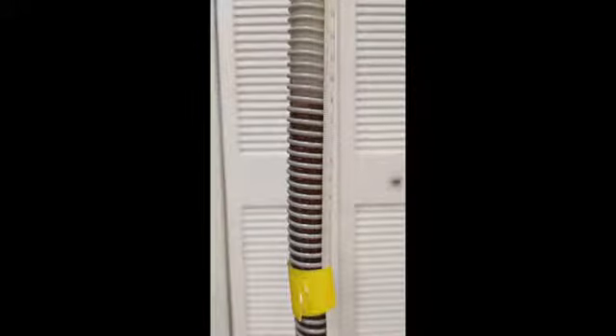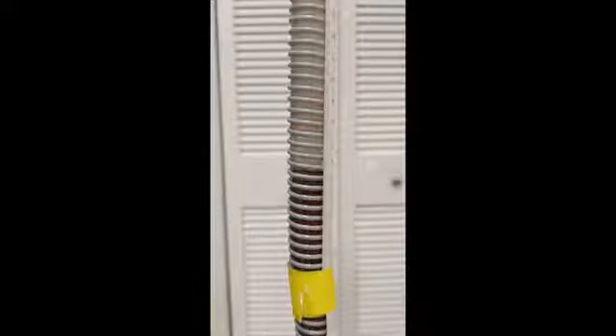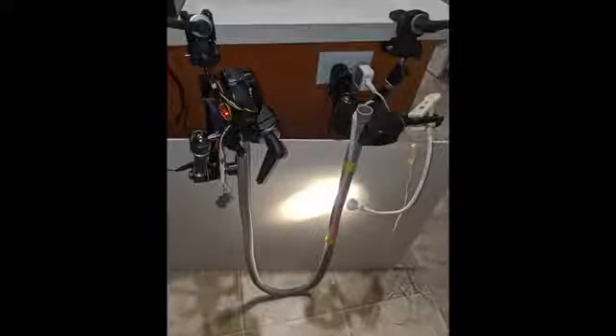I've also done some basic testing of pressure that's possible with this blower, and this shows the blower oscillating between about 10 centimeters of water and 20 centimeters of water at a rate of 16 cycles per minute. This is a picture of the basic test fixture for measuring the output pressure achieved by the blower. The U-shaped tube is filled with liquid, and the blower is blowing into the top of one end of the U and measuring the distance that the liquid on the other end of the tube is being pushed up. This gives me a conversion of air pressure into centimeters of water, which is what's commonly used in respiratory devices.